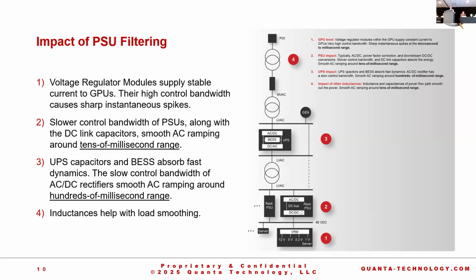They have high bandwidth converters, and as a result, all the high frequency microsecond-level changes will be at that level. The second phase, number 2, is the power supply units, mainly responsible for converting the low voltage AC system, let's say 415 to 480 volt, to the DC side, which could be 48 to 51 volt, depending on the state of the PSU.